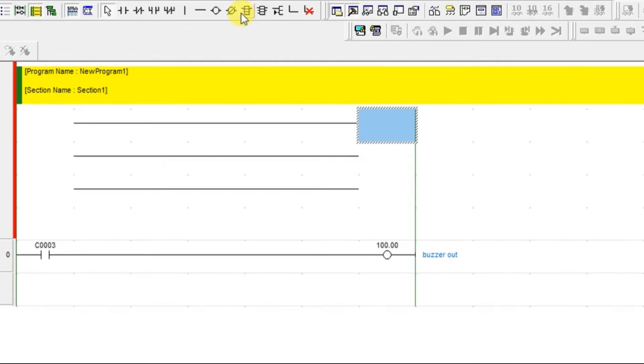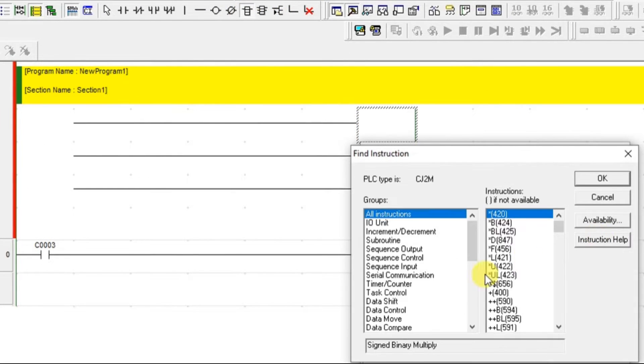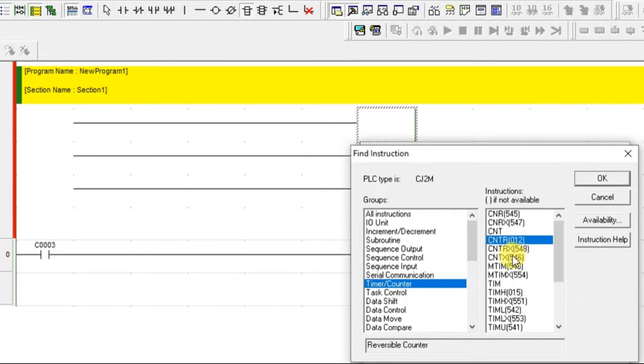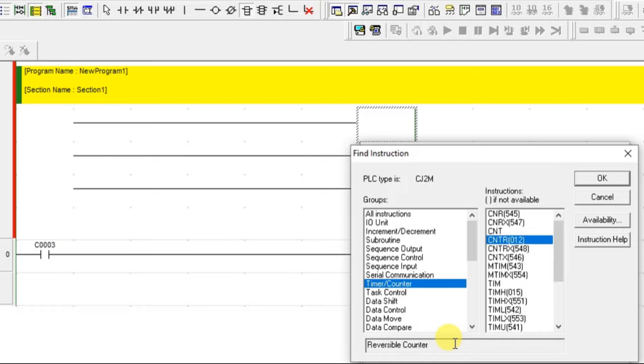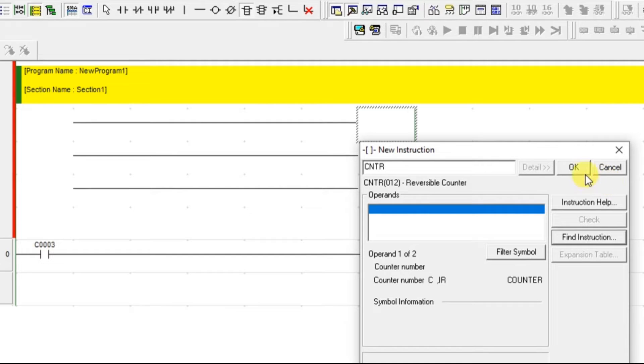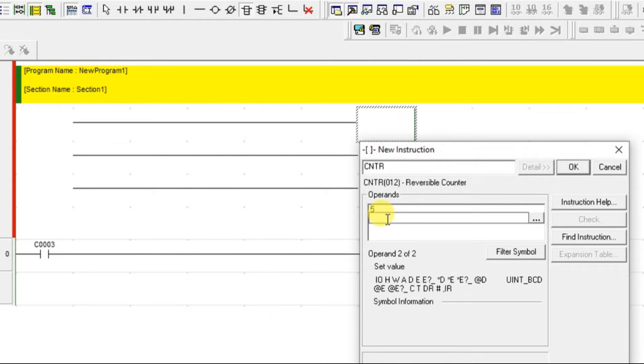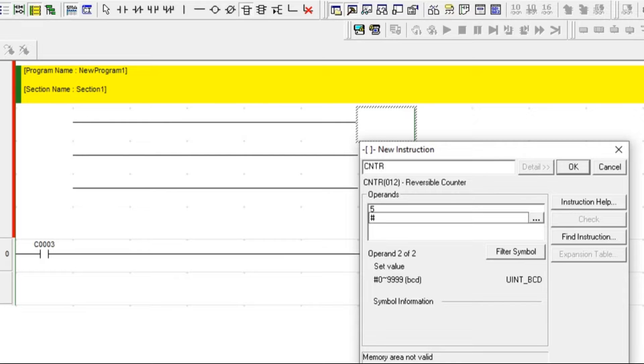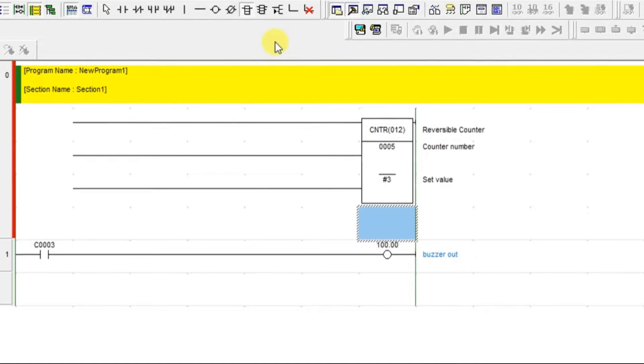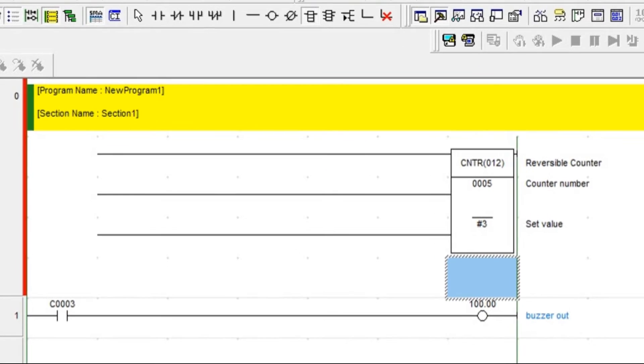Let us take one empty instruction, go to details, find instruction. Here we are having CNTR. Up-down counter is called as reversible counter in OMRON. Click OK and you need to give the timer name. I am giving the timer number as 5. And what is the count limit? I am giving 3. Click OK. The block is ready.